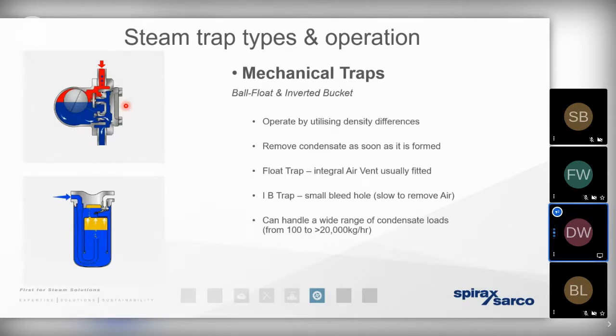We also encourage you to lag a mechanical trap because, as you can see, there's always going to be a certain amount of condensate held back. And if that condensate were to freeze, that's when it's likely to cause damage to the trap mechanism itself. So lagging or a little bit of trace heating is always recommended if these traps are going to be left outside for long periods of time.